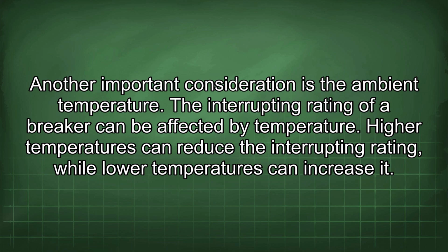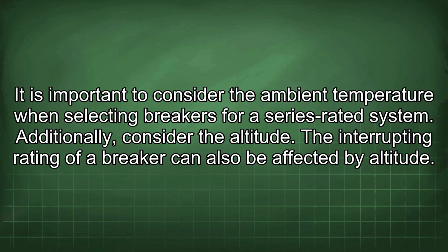Another important consideration is the ambient temperature. The interrupting rating of a breaker can be affected by temperature. High temperatures can reduce the interrupting rating, while low temperatures can increase it. It is important to consider the ambient temperature when selecting breakers for a series-rated system.